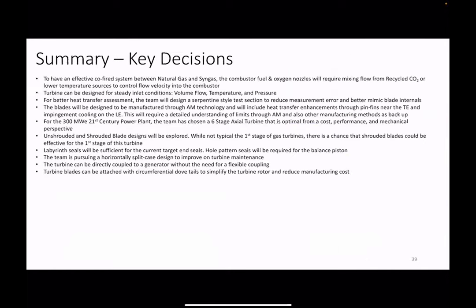So key decisions we obtained during this program: to have an effective co-fired system between natural gas and syngas, we'll require some mixing in the fuel and oxygen nozzles to maintain velocity. We can design the turbine for steady inlet conditions - volume, flow, temperature, pressure.